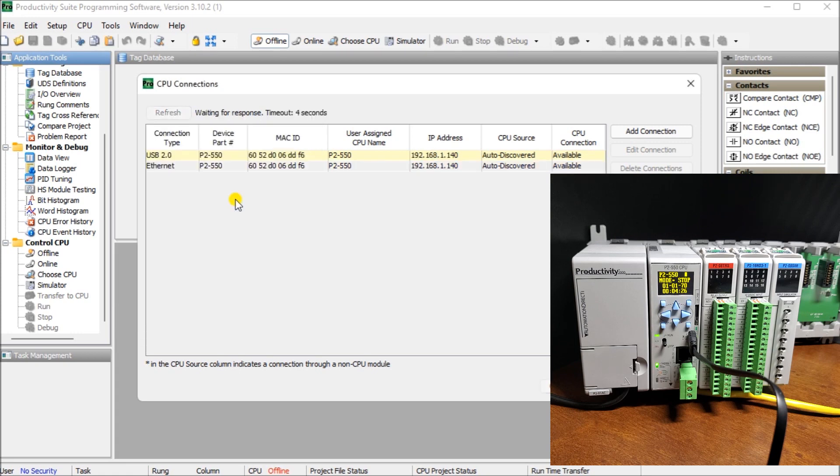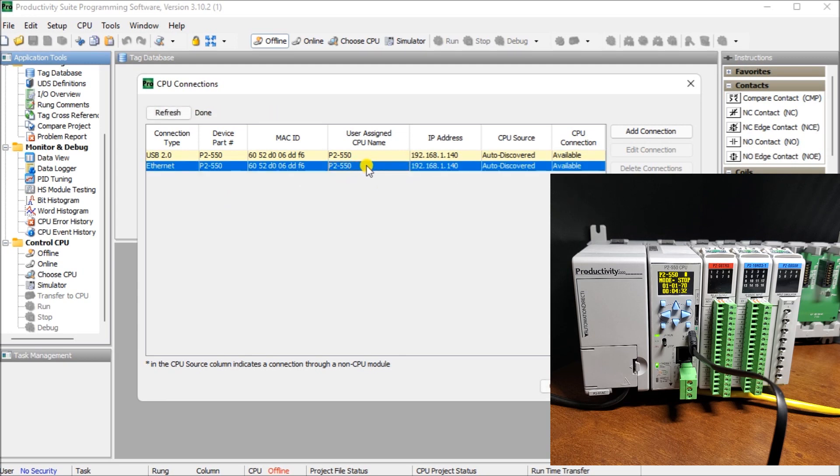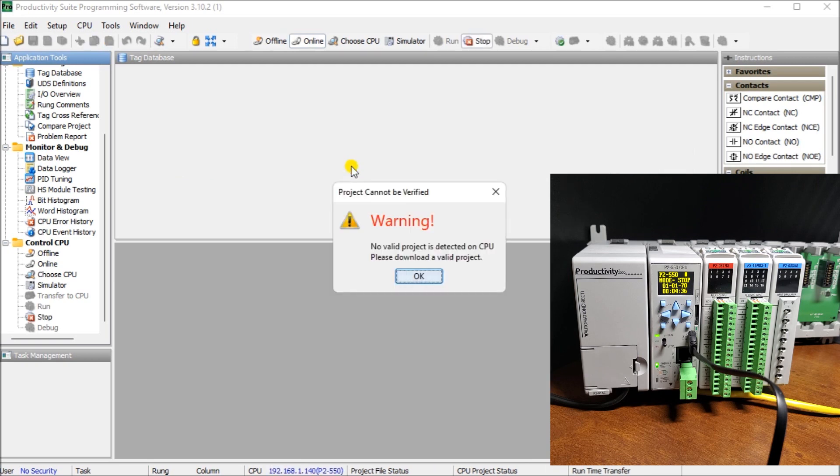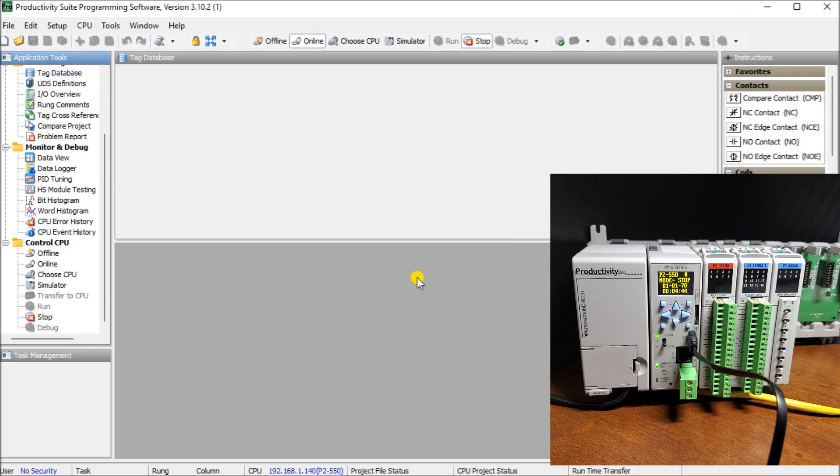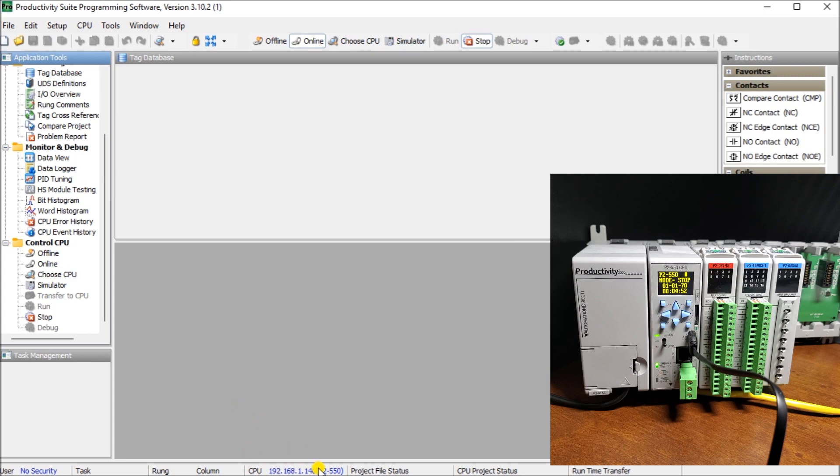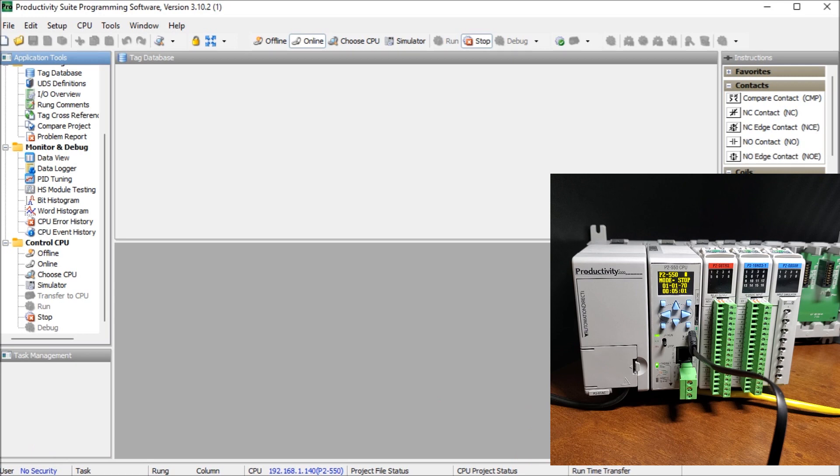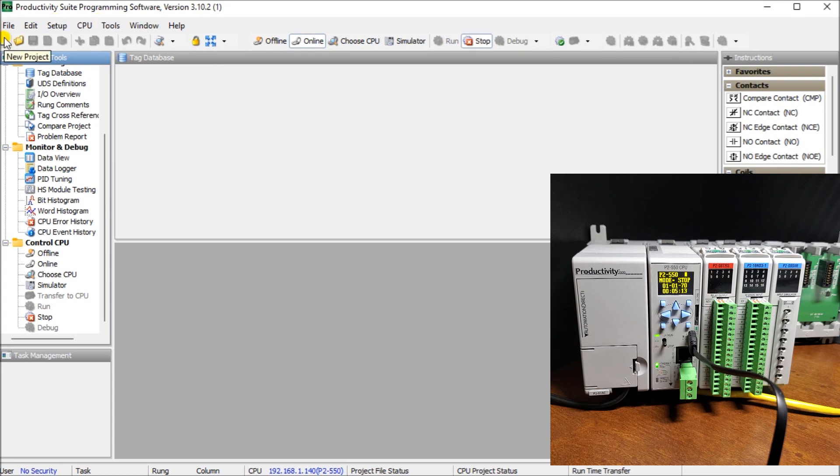Now what it's doing is it's processing there. It's changing the IP configuration through our ethernet port to our controller. There we go. And what you'll notice now is that we have our new IP address. So we can double click on the actual ethernet. And now what you'll notice is it'll say a warning because we don't have a valid project inside the PLC itself. We'll just say OK. And you can see at the bottom of the screen, we are connected. You know it's ethernet because we have our 192.168.1.140 IP address. And you can see here that we have no security, runtime transfers OK. And we can see our controller stopped and we are indicating that we're online to it.